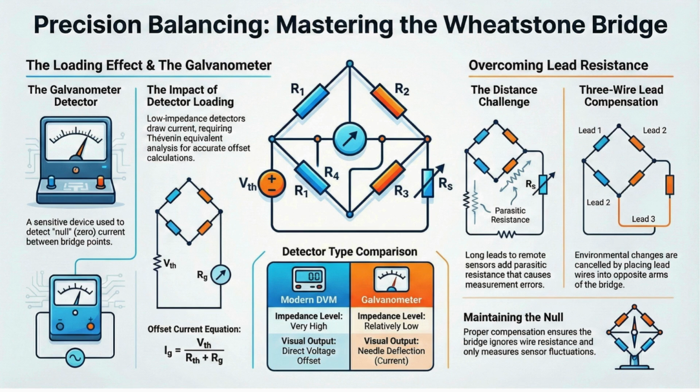The Siemens 3-wire system. Instead of 2 wires to the sensor, you run 3. Wait, wouldn't more wire just add more resistance? It's all about geometry. You arrange it so 1 wire carries power, but the other 2 wires are placed in opposite legs of the Wheatstone bridge. So one wire is in the sensor's leg and the other wire is on the opposing side of the bridge. Exactly. Think of it like a balance scale. If you add weight to both sides at the same time, nothing happens. The balance stays level. That's lead compensation.